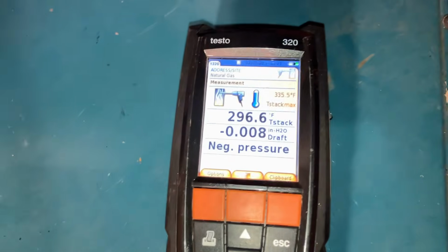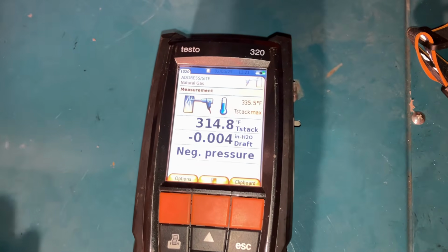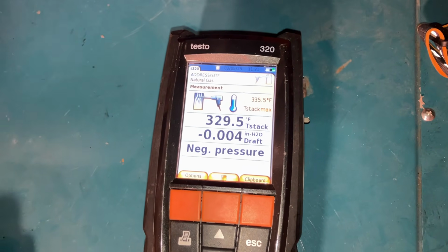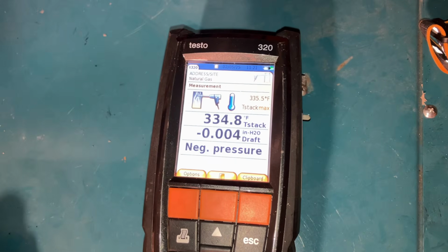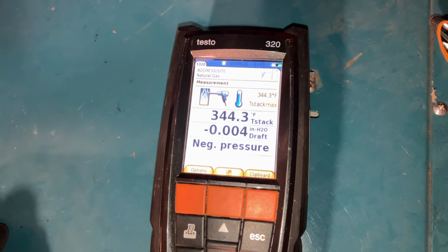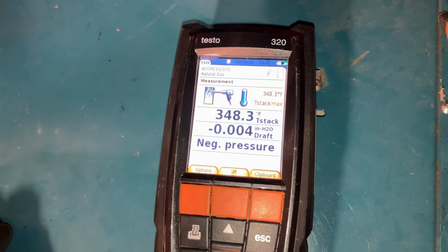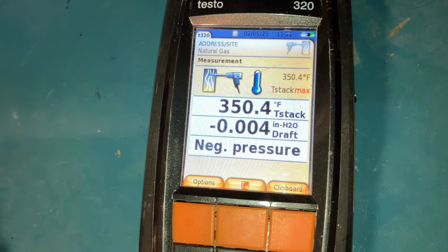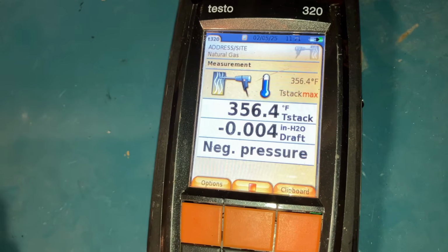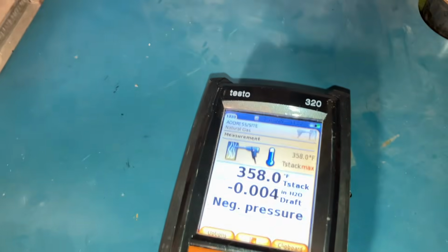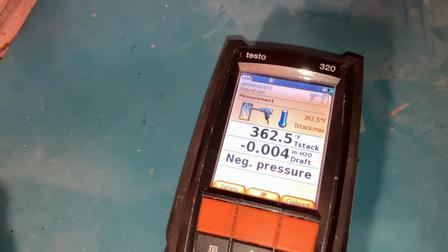And to show you that there's no difference, I'm also going to test draft there, in a hole I just drilled. Okay, check this out. Probe is in. We're going to let that get to the temperature or near to the temperature where it was before, which was roughly 400 degrees of stack. We have negative pressure of 4 thousandths. Keep that in your mind. Once we get to around 400 degrees, we're going to clipboard this, and I'm going to take a test result right there. And then you're going to see that Mikey Pipes, you're right. Or this could be that once in a blue moon where it's different.